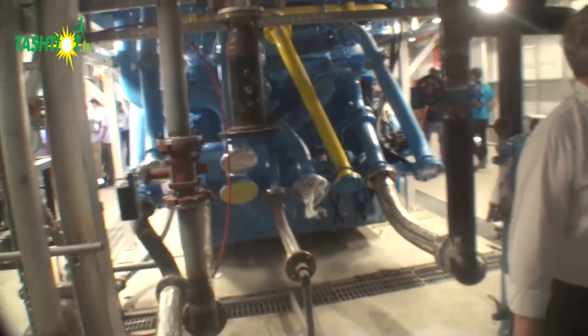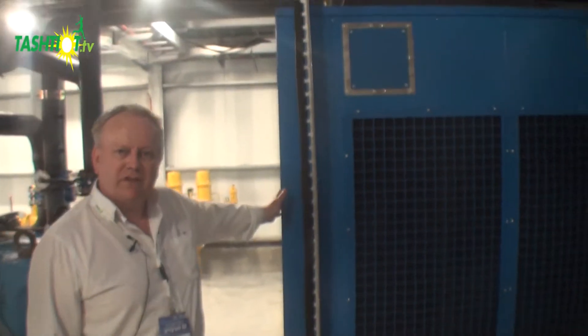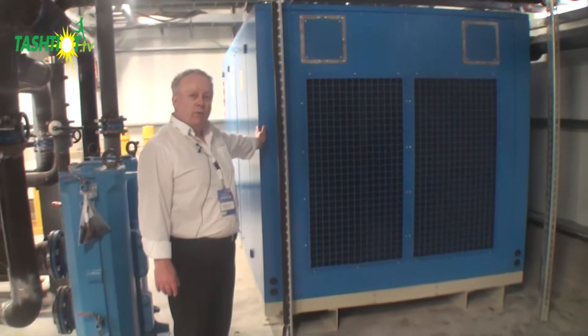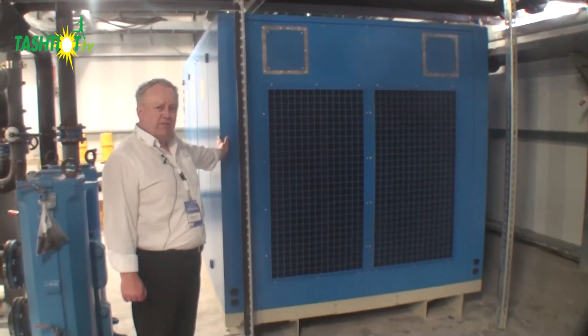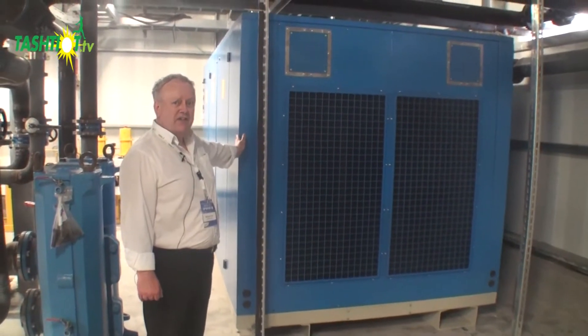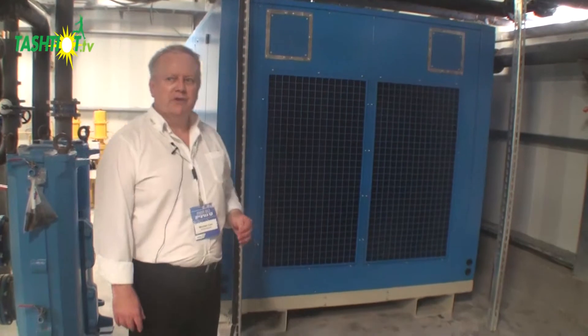Here is a gas compressor needed for this facility. The gas supply is only 2 bar, and we require approximately 5 bar for the engine to function, so the gas compressor is needed. Ideally, if you have a higher supply pressure, you won't need that compressor.